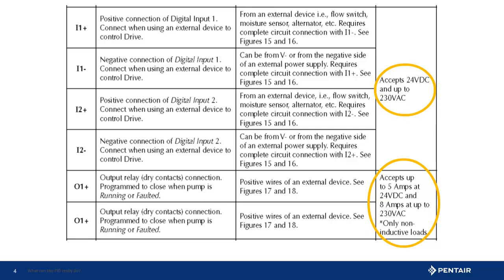So how much of a signal is needed? For the inputs, it is only looking for voltage, not amperage. Voltage, be it 24 volt, alternating current 115 or 230. Why no amperage? Because there is nothing to run. Remember, the input tells the drive program what to do.